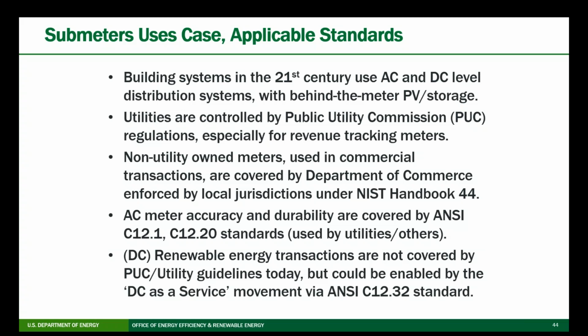So for the AC meter world, ANSI C12.1 and C12.20 are what are used by utilities and others for accuracy. A new standard, ANSI C12.32, didn't exist before, and it's on the verge of being published now. I've worked with a group for about the last 3 years, and we're very close to publishing this, but there will be an American ANSI standard for commercial transactions of DC energy. So when you sell sustainable RECs, you can get paid for the DC energy. When you have a storage system or other way of moving DC energy back and forth, that can be done with submetering in the DC world.